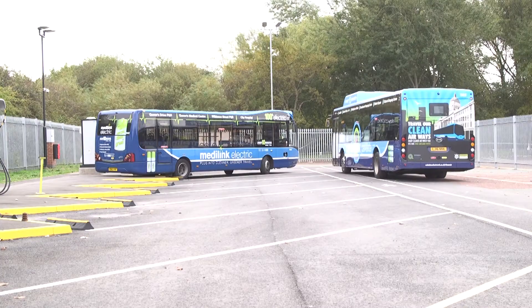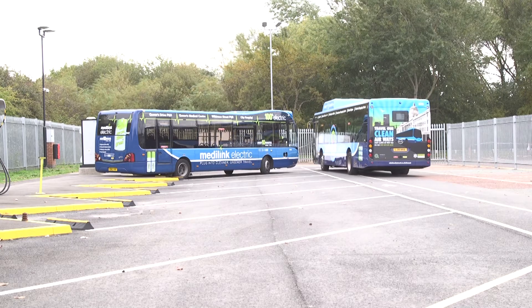One of the things people need to look at is what power aggregators can do for you. I've got an allocated supply of 960 kVA from WPD on this site — there's nothing charging here now, so that supply is just buzzing around. In future, I want to say to a power aggregator: you can take all this power in the day, reserve it for someone else, I won't need it till 11 o'clock at night — and you can make money from that and also alleviate pressure on the grid.